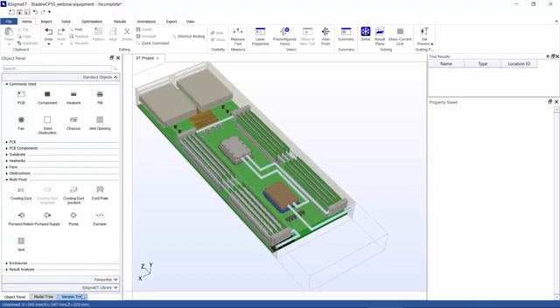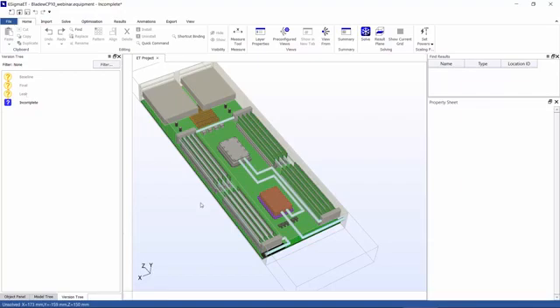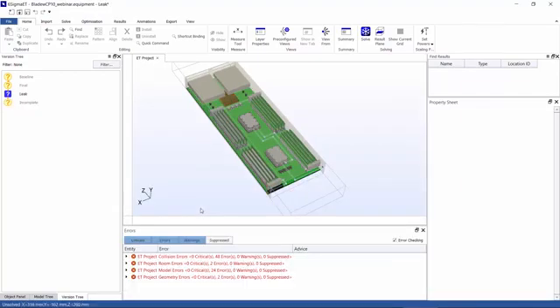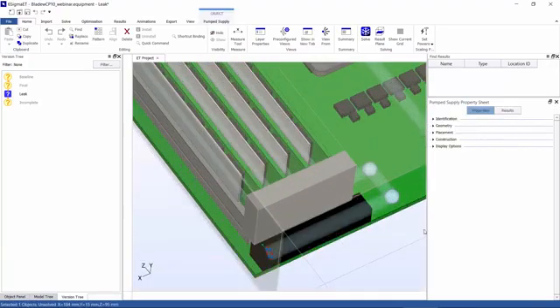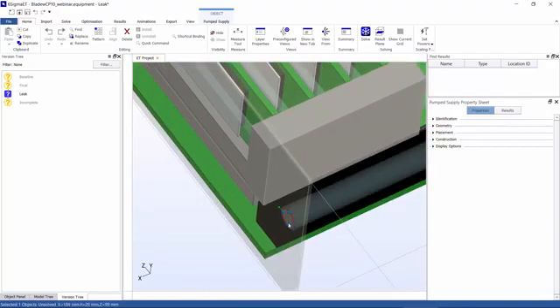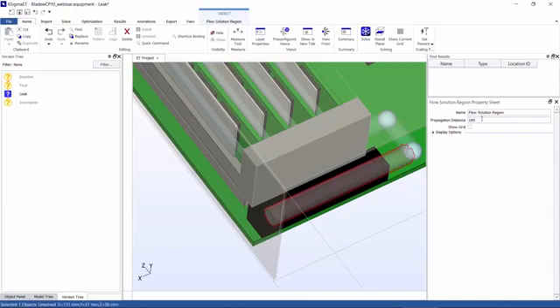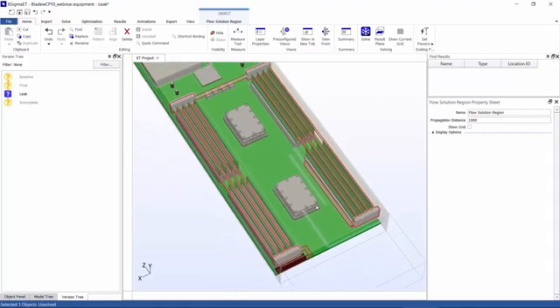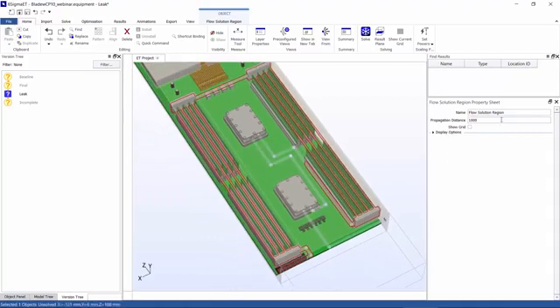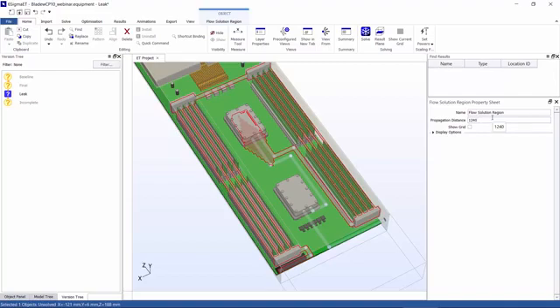So now I want to talk about leak detection. There's a simple and easy method for leak detection using our flow solution object. Some of you may already be familiar with the flow solution regions—we've used those to figure out where our leaks are occurring. We can do that by navigating to our pump supply and just add a flow solution region here. And now we can actually step through the liquid cooling domain and discover where the fluid is flowing. In this case I've increased it all the way to a thousand, and that steps it through one thousand grid cells. I'll go ahead and increase that a little bit farther, and here we see our leak. So it's a very easy to see and visual way of finding the leaks.